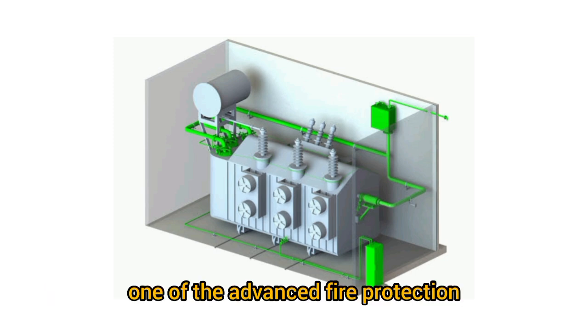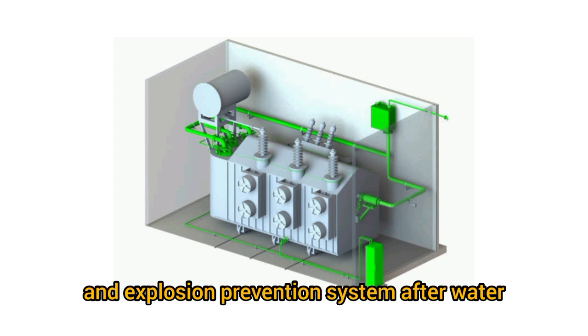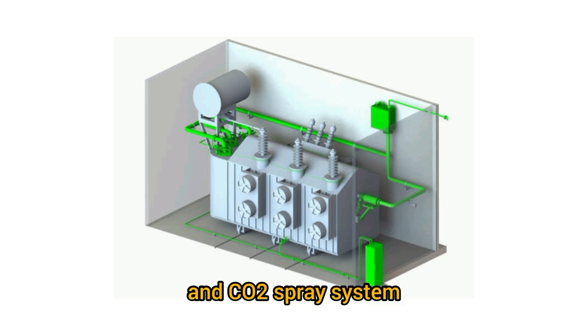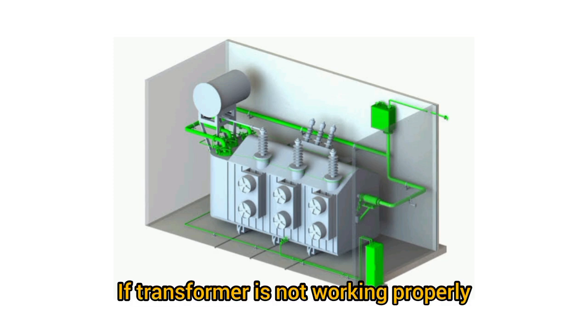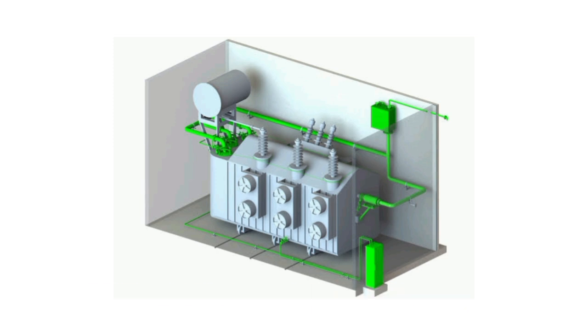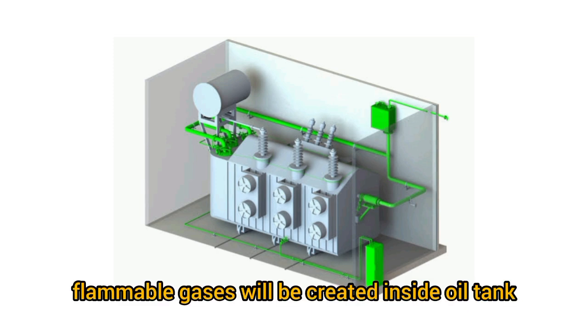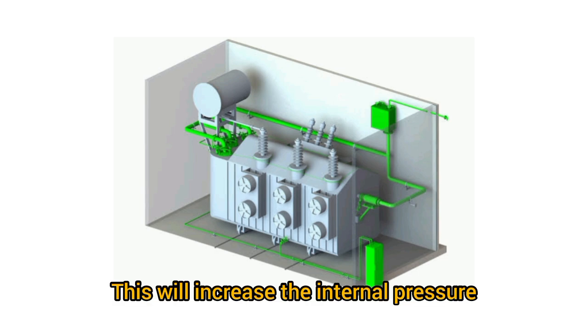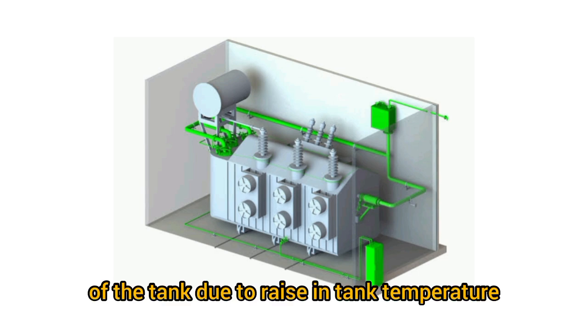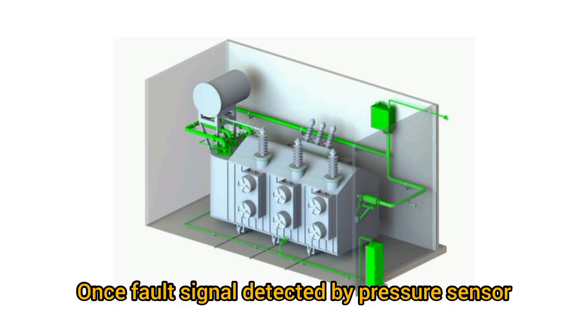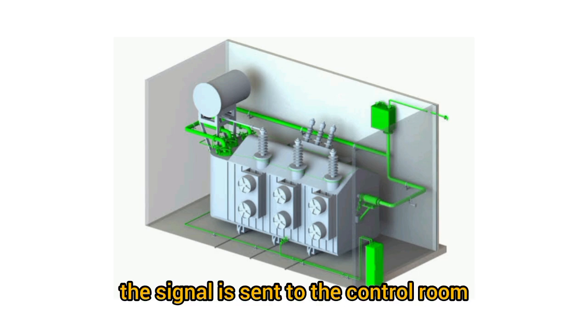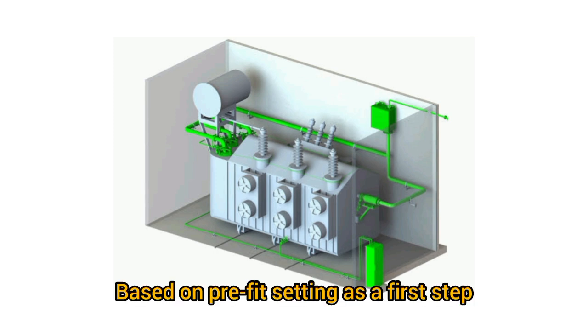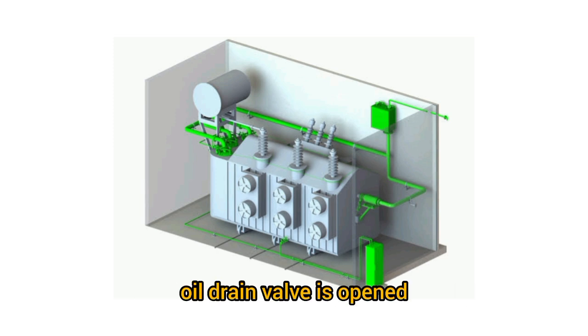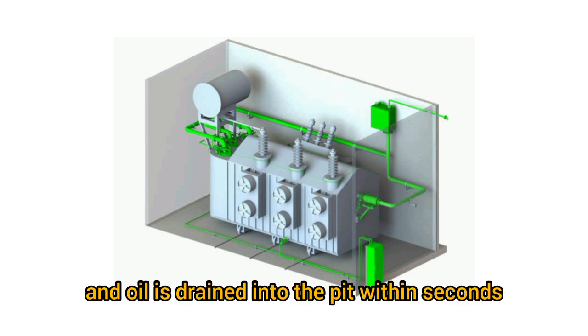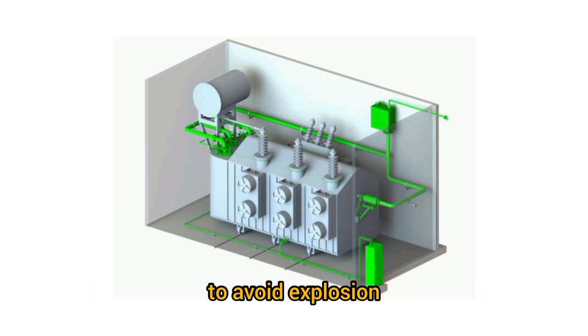One of the advanced fire protection and explosion prevention systems, after the water and CO2 spray systems. If the transformer is not working properly, flammable gases will be created inside the oil tank. This will increase the internal pressure of the tank due to the rise in tank temperature. Once a fault signal is detected by the pressure sensor, the signal is sent to the control room. Based on pre-fed settings, as a first step, the oil drain valve is opened and oil is drained into the pit within seconds to avoid explosion.